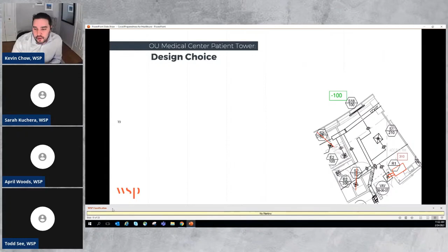In our case, we reduced the supply air inside each of the patient restrooms. We also increased the return air inside the patient rooms to help make that a negative pressure room. We then installed a negative pressure air machine that was HEPA filtered and connected it into the return system, so that all the air coming out of a patient room was HEPA filtered before it went back to the main system.